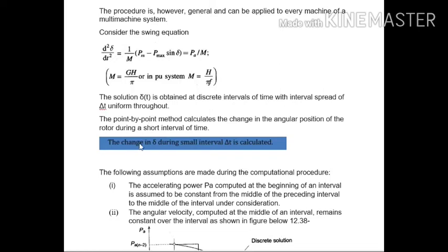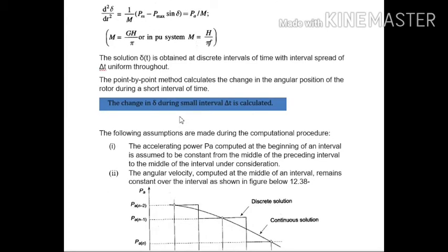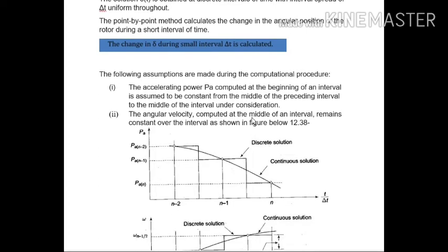The main goal of this method is to calculate the change in the rotor angle δ during a small interval Δt — that is what we are doing here. The method calculates the change in angular position of the rotor during a short interval of time. For that, certain assumptions are made, which are very useful for deriving the numerical solution. The first assumption is: the accelerating power Pa computed at the beginning of an interval is assumed to be constant from the middle of the preceding interval to the middle of the interval under consideration.